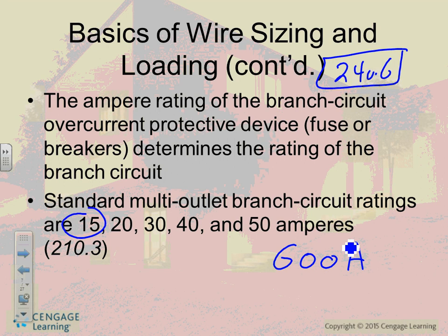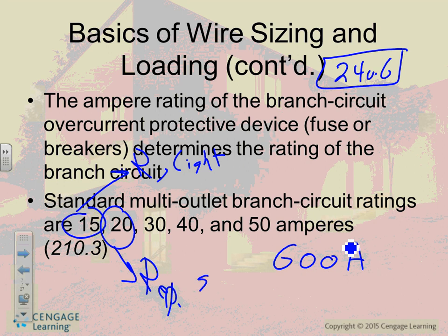The branch circuits that we use for residential are very common. They're very simple branch circuit cables. Let's start with the 15 amps. 15 amp circuits in a dwelling, we feed them for receptacles and lights. 20 amp branch circuits: typically receptacles only in a dwelling, not commercial. In commercial, we don't typically use 15 amp circuit breakers. It's not worth it. So, in the residential, 15 amp is for lights and receptacles. The 20 amps are for receptacles. I call them special.